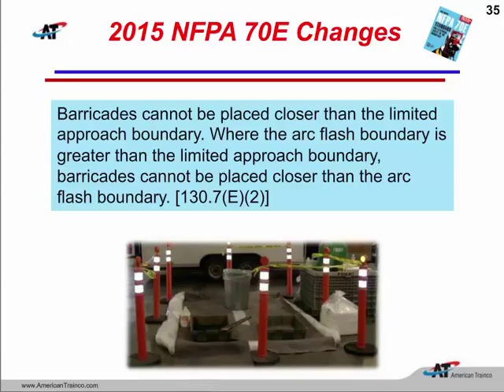So that arc flash boundary, because it is a calculated boundary, many times it is outside the limited approach boundary. So we're going to have to keep those unqualified people away from that, because we do not want them inside an area that could cause them third-degree burns in case of an arc flash or arc blast.